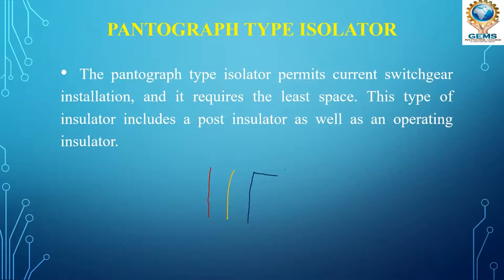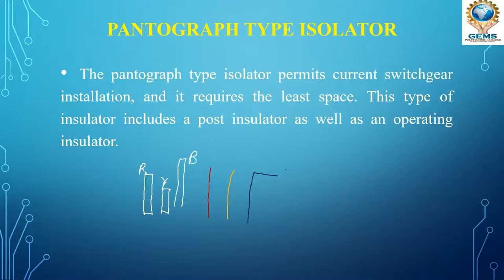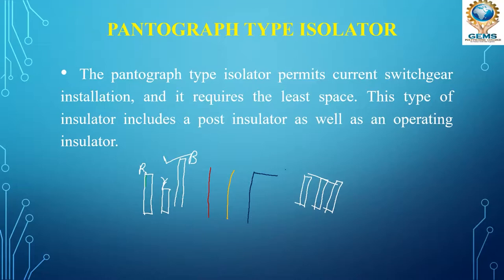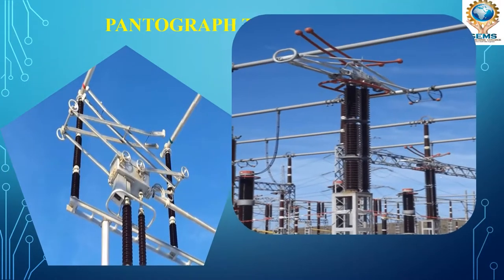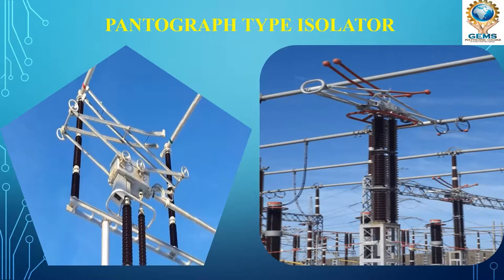If, for example, the R phase has a certain height, the Y phase has a different height, and the B phase has yet another height, using a double break isolator would require equal height for all phases. But if equal height is not available, the pantograph isolator works better in such situations. This is how the pantograph isolator looks — this arrangement is called the pantograph isolator.